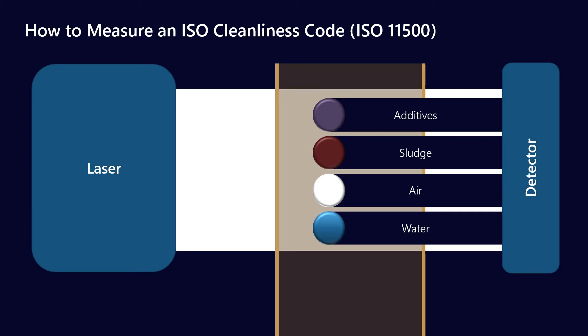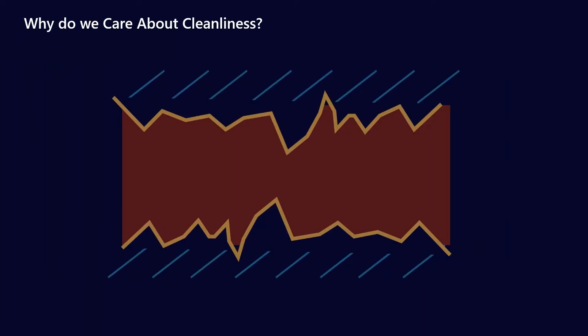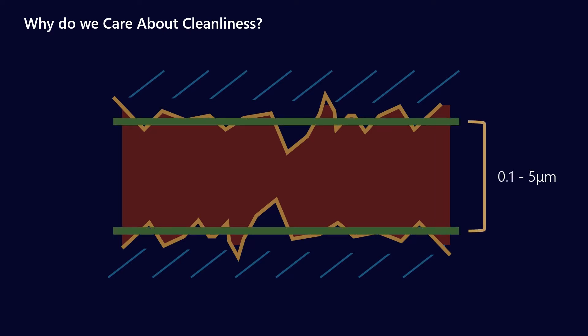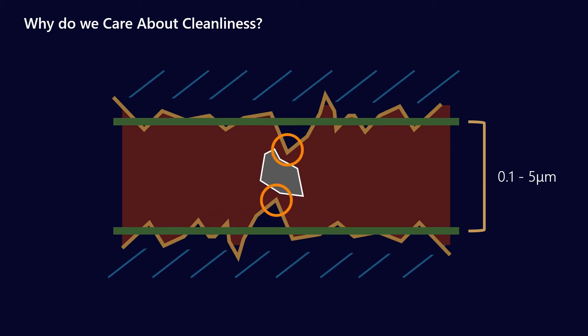Now the question is: why do we want to eliminate these four different types of particles from the count? We need to think about why we care about oil cleanliness. If you imagine a contaminant passing through an oil film which is in the region of 0.1 to 5 microns thick, a contaminant of that order of magnitude will contact surface asperities. That's going to cause two or three body erosion, which eventually leads to micropitting, resulting in spalling, macropitting, and eventually failure. That's why we care about cleanliness — hard particles can lead to damage and failure of our equipment.